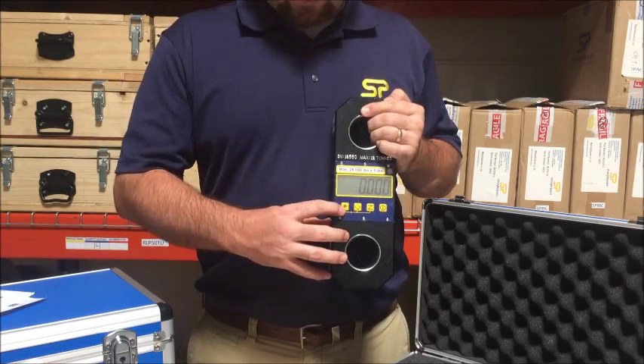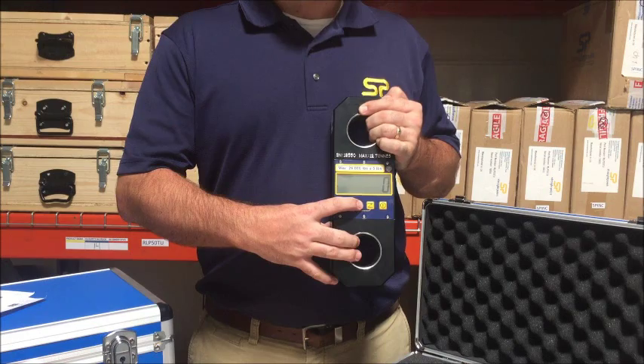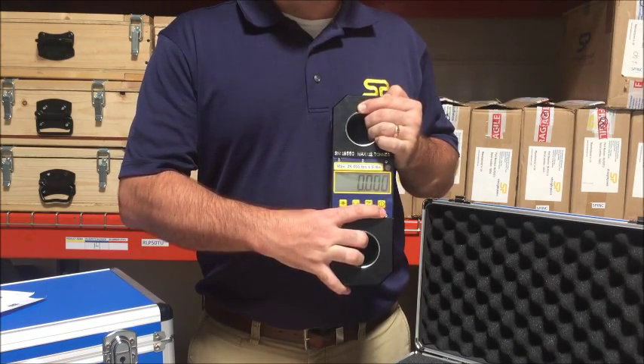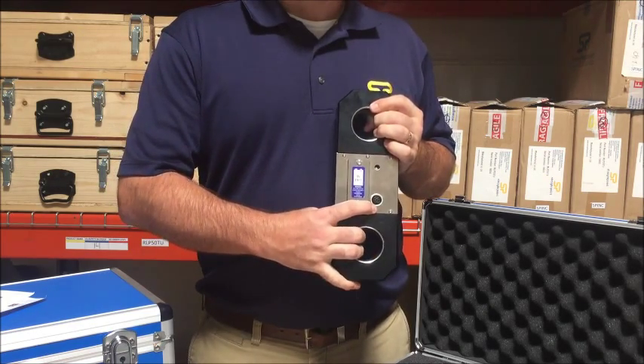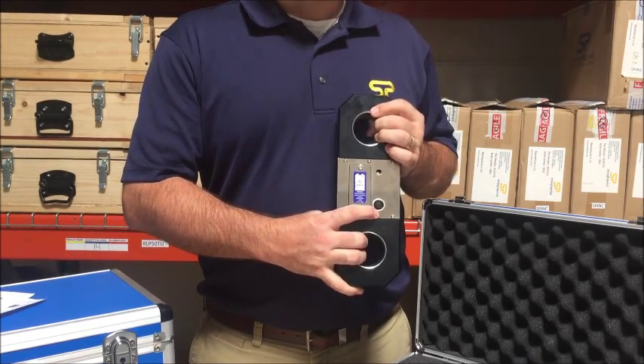Feature buttons include tare and preset tare, unit of measure toggle between kilonewtons, kilograms, pounds, and tonnes, peak hold, and an on and off power button. On the backside, we have a battery compartment for a standard 9-volt battery and RS485 serial output for a cabled handheld option or data logging software.